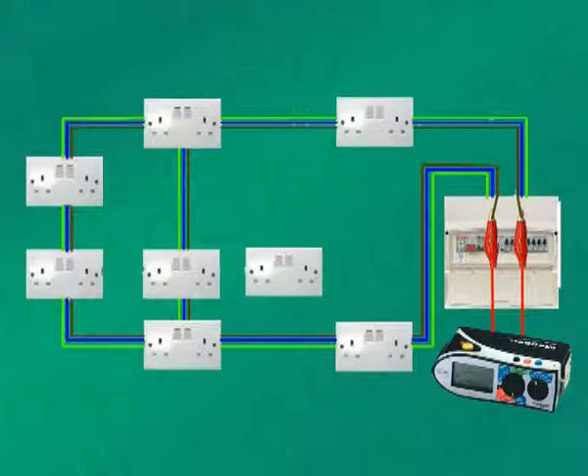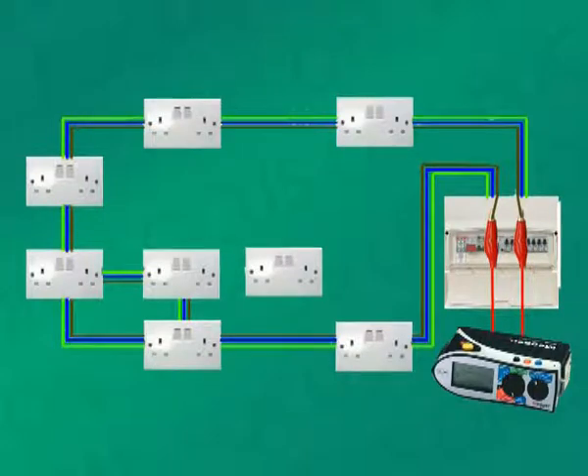This effectively creates a parallel resistance path, so will cause lower resistance readings for the entire ring than you would get for a standard ring circuit. An interconnection could only involve part of a circuit, like this. So again, it provides a parallel resistance, but not involving so much of the circuit.